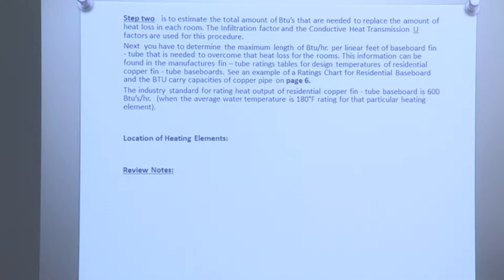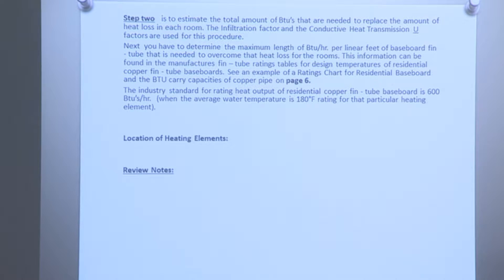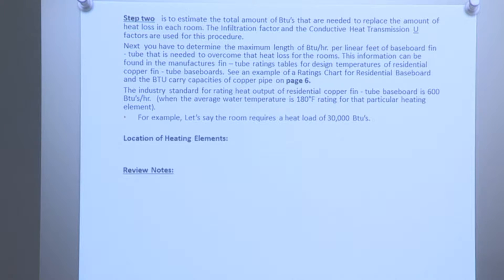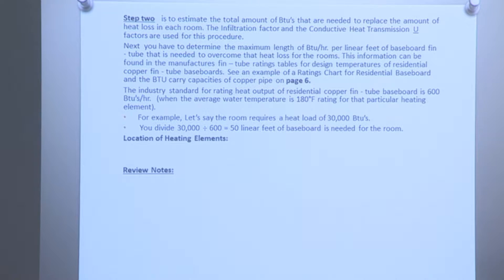Step 2 is to estimate the total amount of BTUs needed to replace the amount of heat loss in each room. The infiltration factor and the conductive heat transmission U-factor are used for this procedure. Next, we have to determine the maximum BTUs per hour per linear foot of baseboard fin tube needed to overcome the heat loss for the rooms. This information can be found in the manufacturer's fin tube rating tables. The industry standard for rating heat output for residential copper fin tube baseboard is 600 BTUs per hour when the average water temperature is 180 degrees Fahrenheit. For example, if the room requires a heat load of 30,000 BTUs, you divide 30,000 by 600, which equals 50 linear feet of baseboard needed for the room.